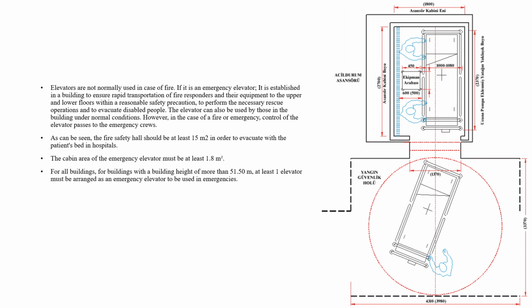Elevators are not normally used in case of fire. An emergency elevator is established in a building to ensure rapid transportation of fire responders and their equipment to the upper and lower floors within reasonable safety precautions, to perform the necessary rescue operations and to evacuate disabled people. The elevator can also be used by those in the building under normal conditions. However, in the case of a fire or emergency, control of the elevator passes to the emergency crews.